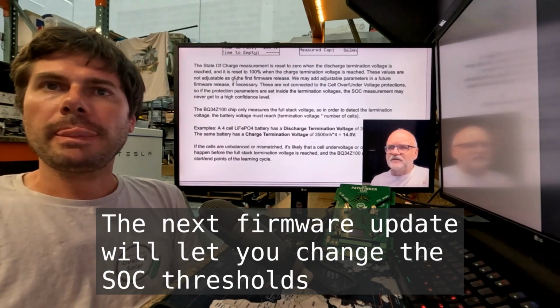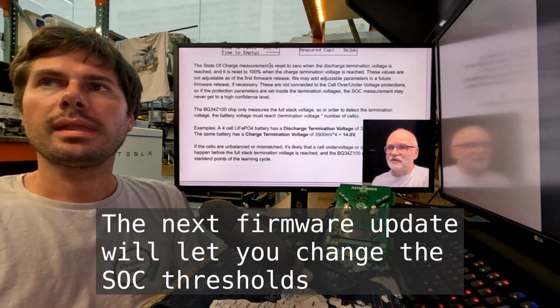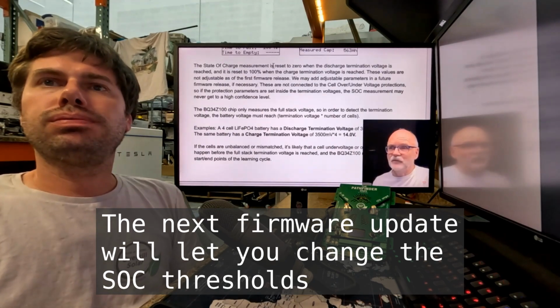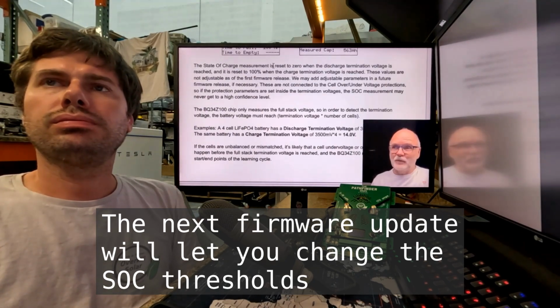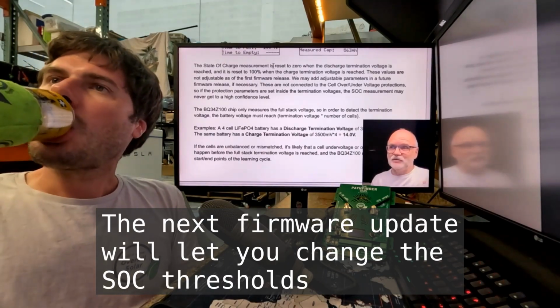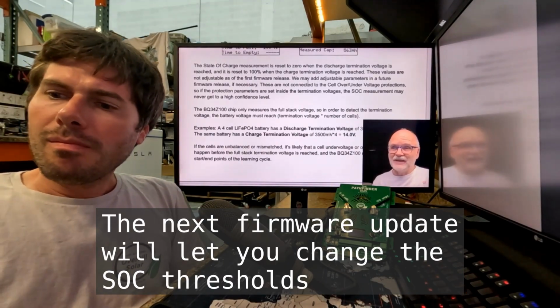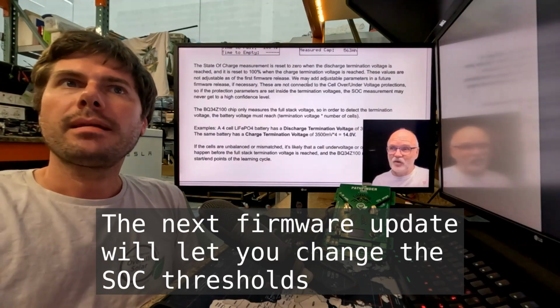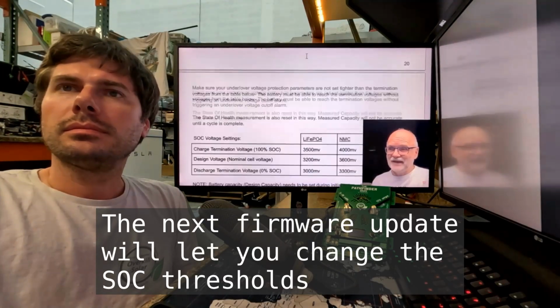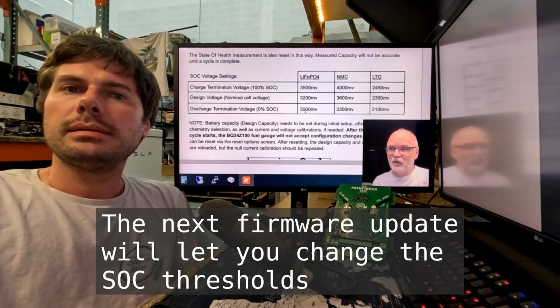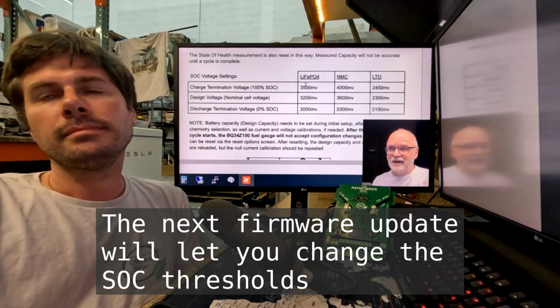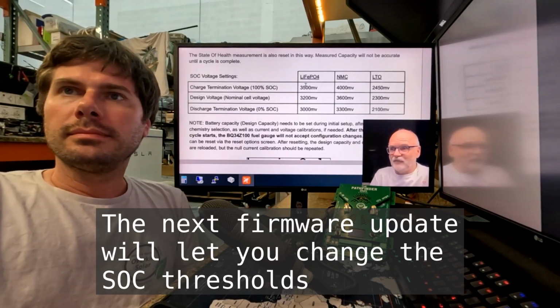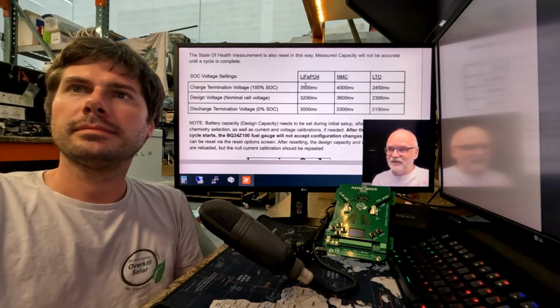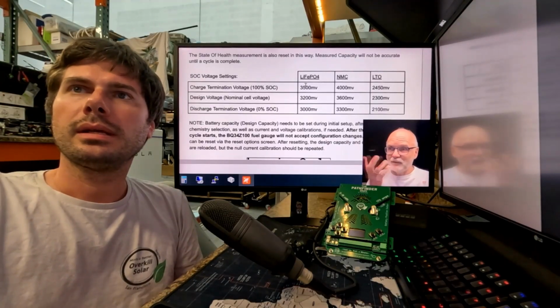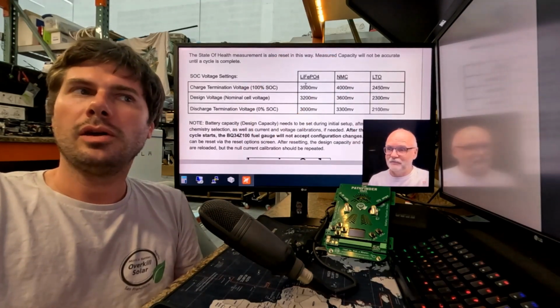The state of charge measurement resets to 0 when the discharge termination voltage is reached, and resets to 100% when the charge termination voltage is reached. These values are not adjustable as of the first firmware release, so it only handles between 3.0 and 3.5 volts. I never charge to 3.5 volts, so this BMS would never reset to 100%. But maybe we already have upgraded firmware here and can adjust these parameters. We'll find out later.